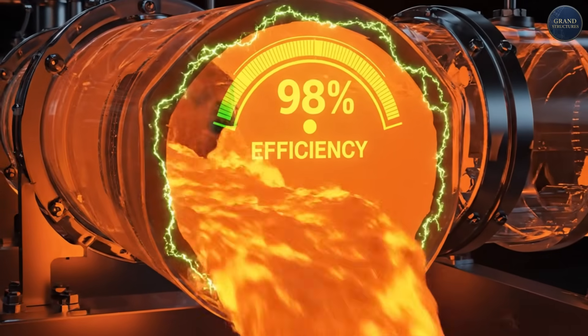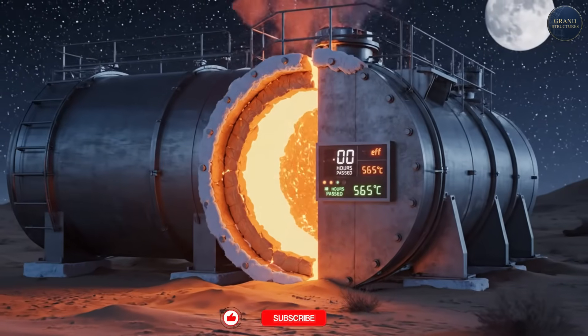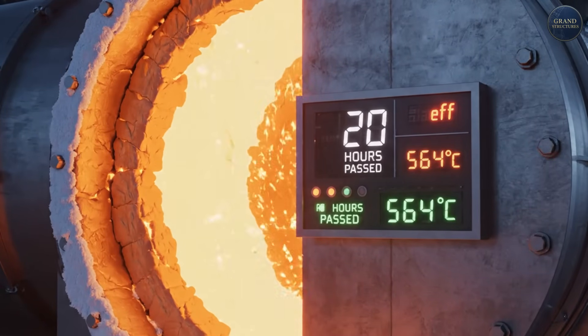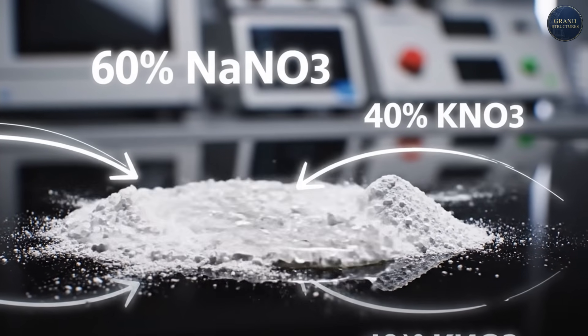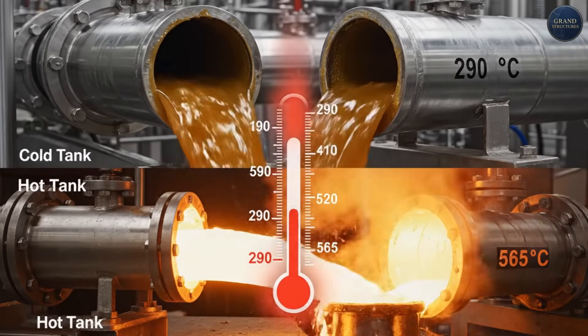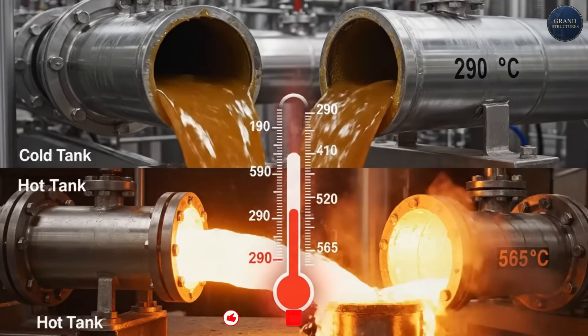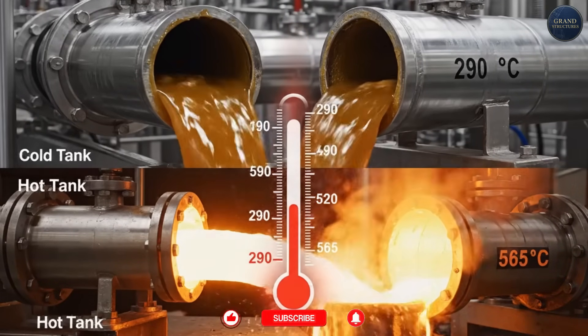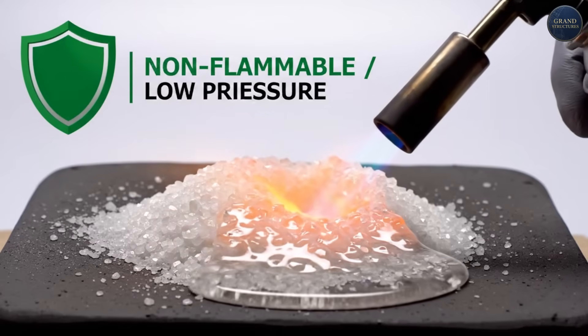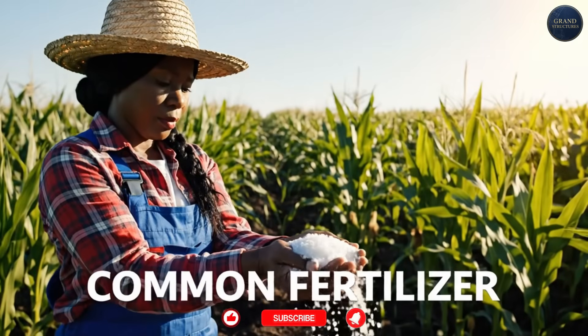Here's the engineering breakthrough: molten salt can store thermal energy at 98% efficiency. You heat it up during the day, store it in insulated tanks, and it loses only about 1 degree of heat per day. The salt mix is 60% sodium nitrate (NaNO3) and 40% potassium nitrate (KNO3), with a melting point of 220 degrees Celsius (428°F). Operating temperature ranges from 290°C (too cold) to 565°C (too hot). This eutectic mixture stays liquid across a huge temperature range without high pressure. It's non-toxic, non-flammable, and dirt cheap — basically fertilizer, the same salts farmers use to grow crops.